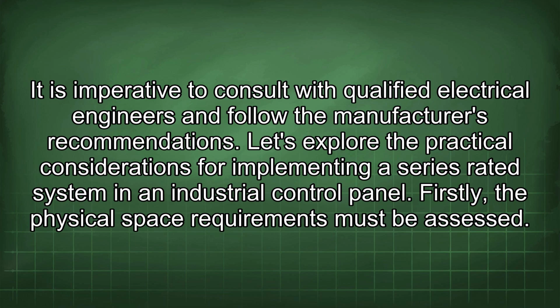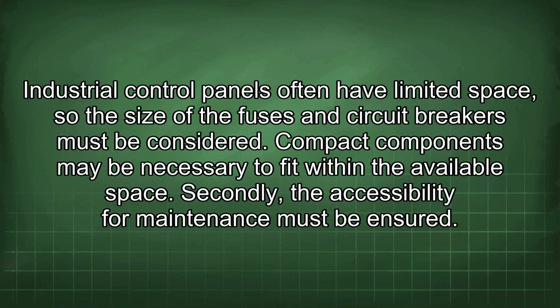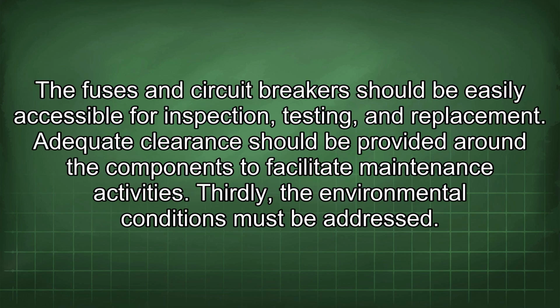Firstly, the physical space requirements must be assessed. Industrial control panels often have limited space, so the size of the fuses and circuit breakers must be considered. Compact components may be necessary to fit within the available space. Secondly, the accessibility for maintenance must be ensured. The fuses and circuit breakers should be easily accessible for inspection, testing, and replacement. Adequate clearance should be provided around the components to facilitate maintenance activities.